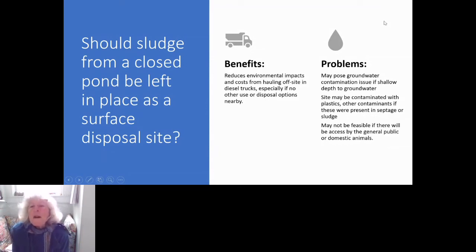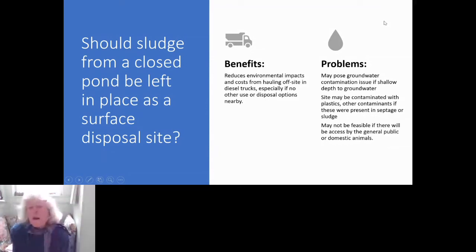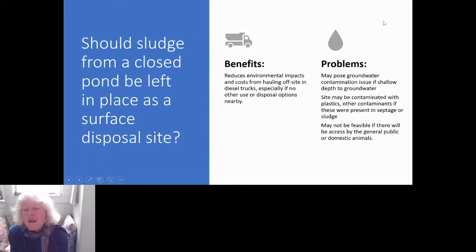The question often comes up with septage from restaurants — if they get septage that is mainly toilet flushings and food waste, is that commercial or domestic septage? Because it has a large amount of other materials being flushed down, we'd call it commercial septage, so it would not be under 503 and would be subject to RCRA requirements for solid waste. Also, if the site is accessible by the general public or planned to be converted to another use with public access, surface disposal may not be feasible. We had an issue where land-applied biosolids sites were sold and residential development moved in, making it hard to meet public access restrictions.